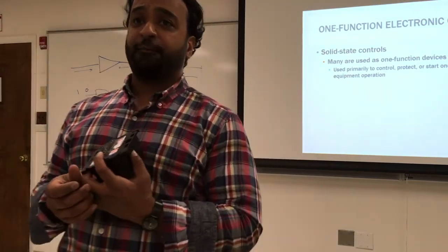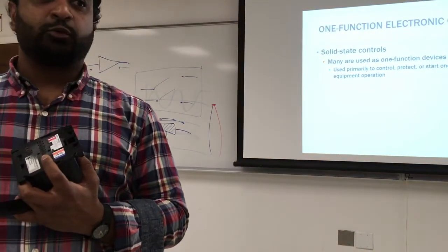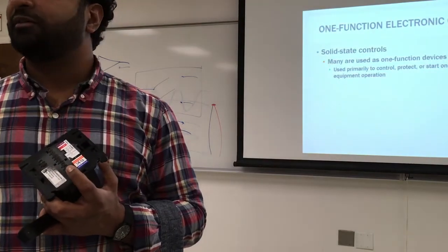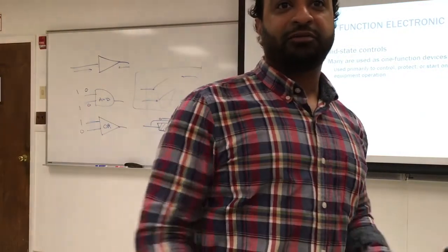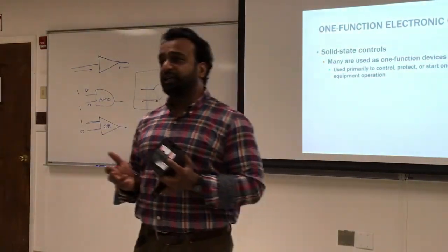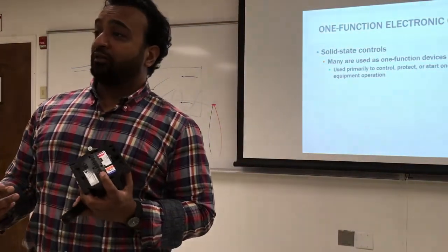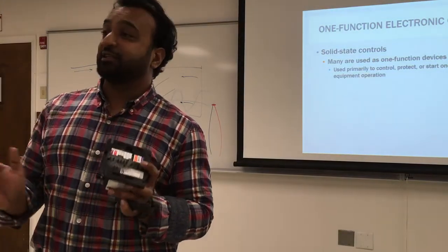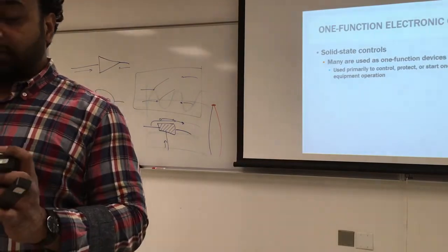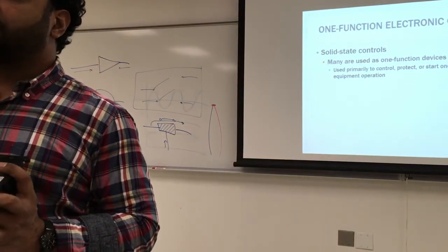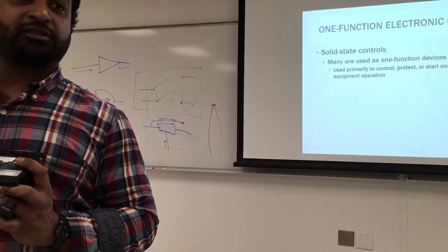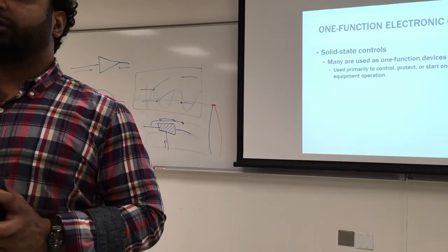There's a 15 second delay before the oil valve comes up. We want to make sure the motor is running, there's air, and there's also something called pre-purging. I want to get rid of all the air inside the chamber, whatever it is, moisture, residual smoke, and get fresh air. 15 seconds is enough. When we go to industrial, it's going to be more involved for these little small processes. We turn on the ignition and motor, give them 10 seconds, then the oil valve will open up. What's going to come into the chamber? The atomized oil. And we wait for the fire.